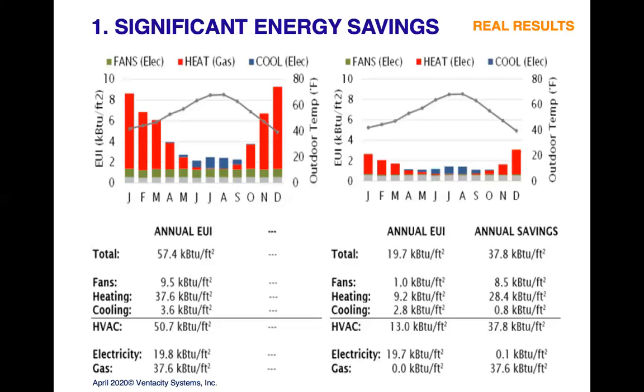One of the big takeaways that's really powerful, especially for the utilities when they're talking about these retrofits, is if you look beforehand, we had electricity at just under 20 kBTUs per square foot on the EUI, gas at 37 and electricity at just under 20. When we completed it, we had the electricity at just under 20 still, so let's call it virtually unchanged, and the gas was gone, it was 0. So we eliminated the gas, but we didn't load shift onto the grid with electric, and that makes utilities very happy.